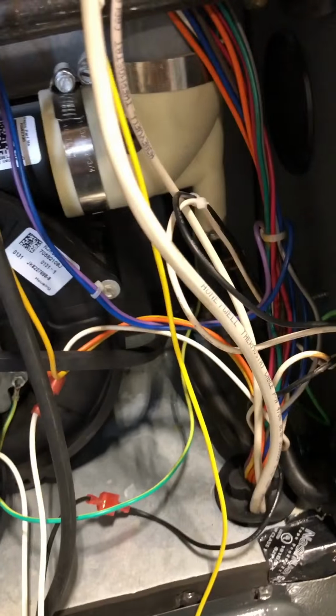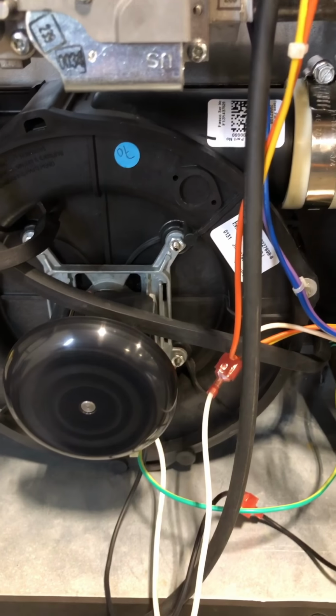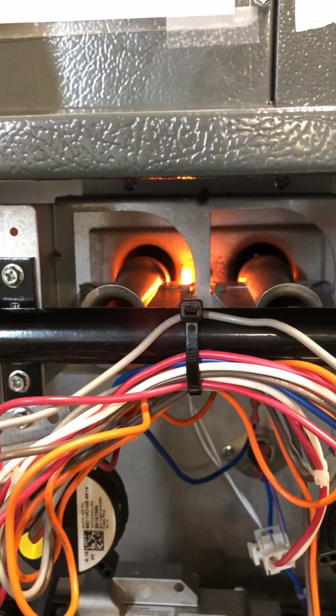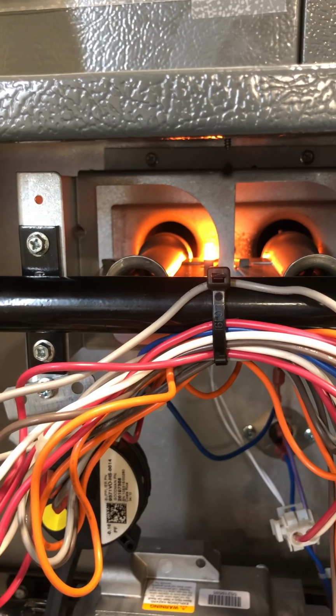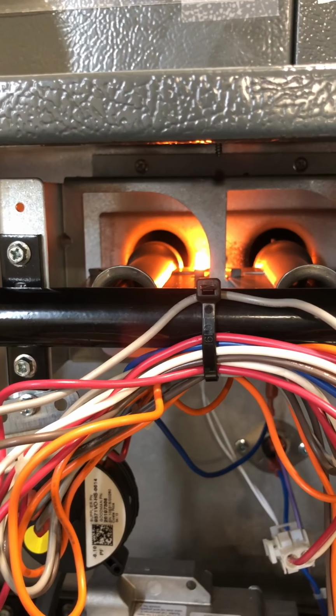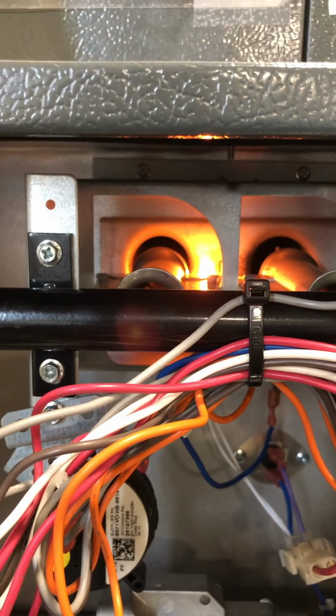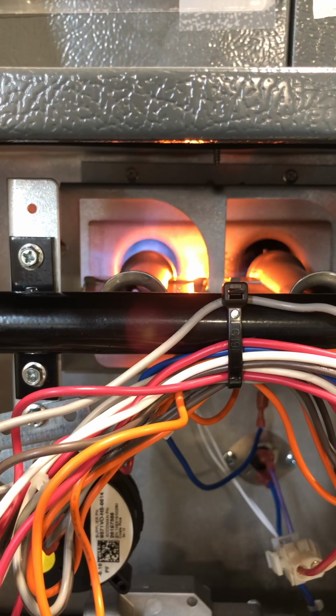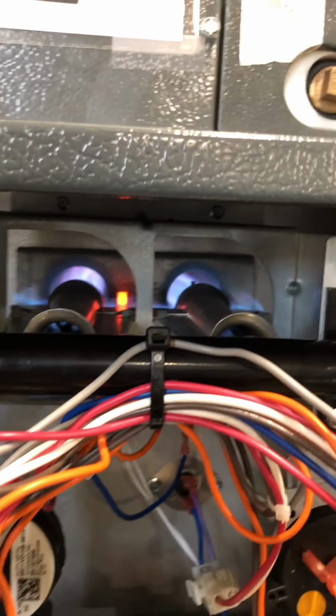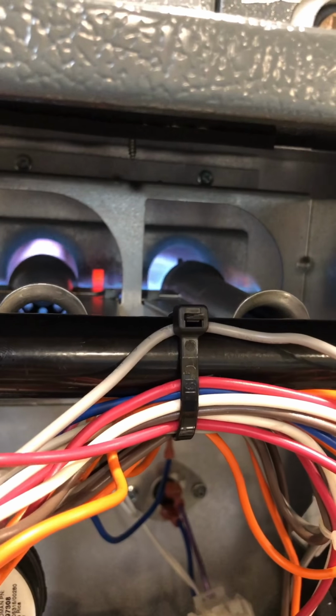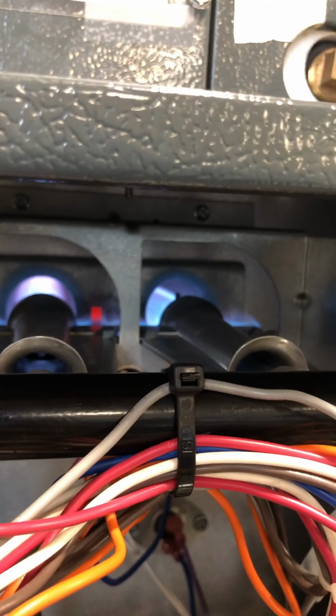Well, that was bad TV. No, I just had my meter zeroed out on me, so I had to zero it back out. Pulling plenty of vacuum on that switch. Then we're going through the process. Hot surface ignition. Flame. 24 volts to the gas valve, which creates the flame. And we are verifying flame with the flame sensor. Gas valve will stay on. Blower motor.